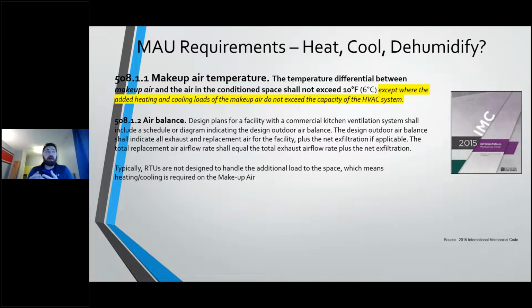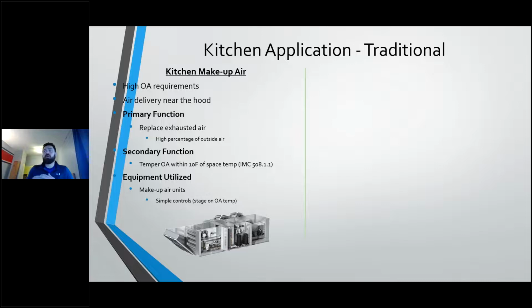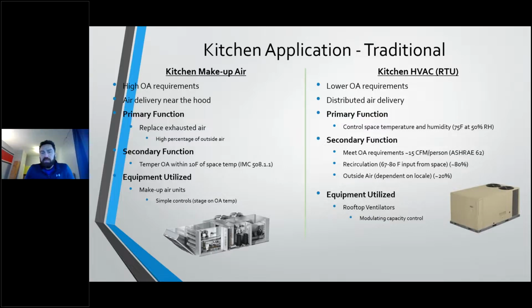So what we're seeing across the country is small mom and pop shops, people that are just getting their restaurant open, whether that be here in Minnesota or in Wisconsin or I'm sure in Alaska. If people like that are just getting the place open, they're just doing heated makeup air. They're not doing any cooling. They're doing more middle of the road budgets, or university style places or places with large HVAC systems, are sticking with a more traditional kitchen application. So that traditional kitchen application is a kitchen makeup air unit with a primary function being to replace the exhausted air, and the secondary function being to temper that air within 10 degrees of the space temp, and then utilizing a rooftop unit with a primary function of controlling the space temperature.